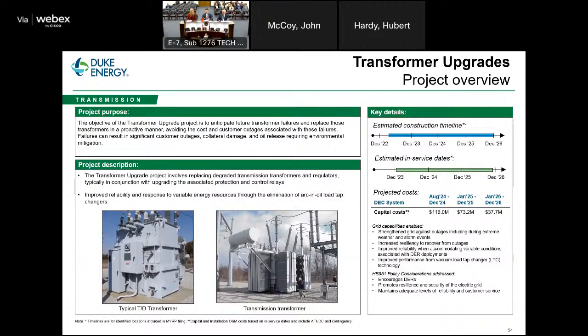And the load tap changer, or voltage regulation component, is often the location of a failure when we do have a transformer failure. We are actually upgrading that technology, again similar to circuit breakers that use an oil technology. The new regulation or load tap changer technology that would be industry standard now is a vacuum-based technology. When you have a vacuum chamber within this load tap changer, you actually eliminate the possibility of arc gases building up and leading to catastrophic failure. So I say all that to say our upgrade is not just resetting the life expectancy, it's really eliminating a significant failure mode for our transformers on the grid.